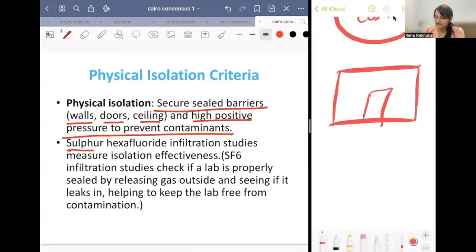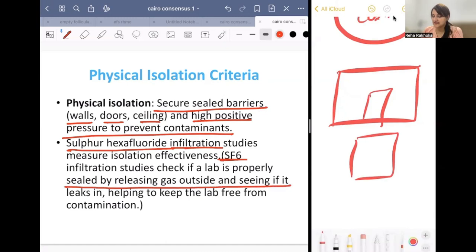What is SF6 used for? SF6 infiltration testing checks if the lab is properly sealed by releasing the gas outside the lab and checking inside to see if it leaks in. If it's not leaking, that means the IVF lab is properly sealed.